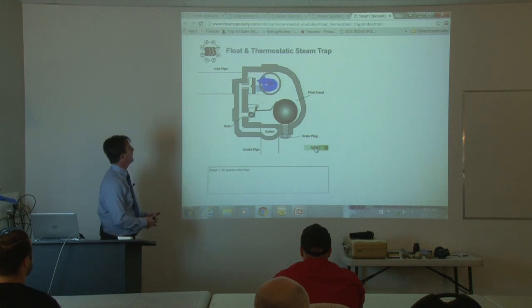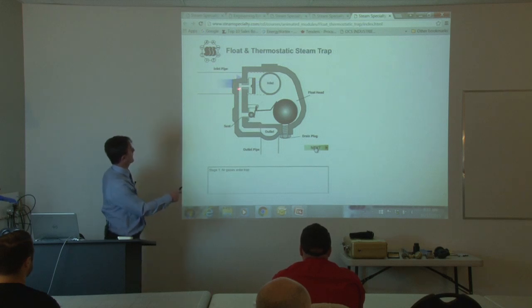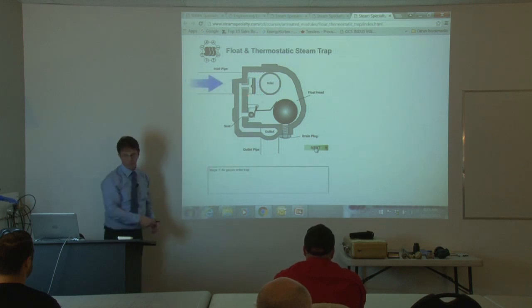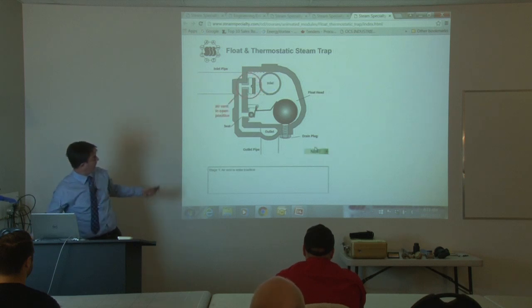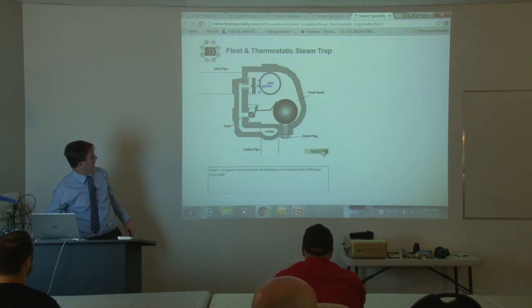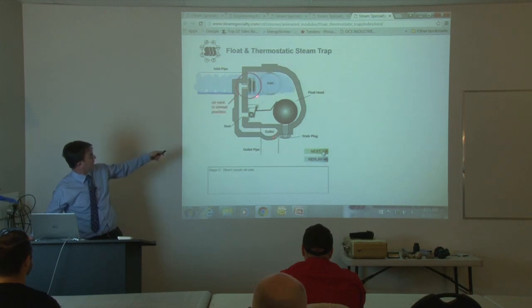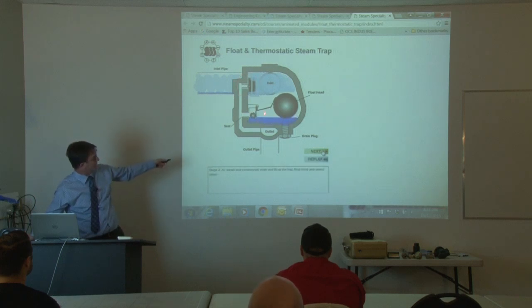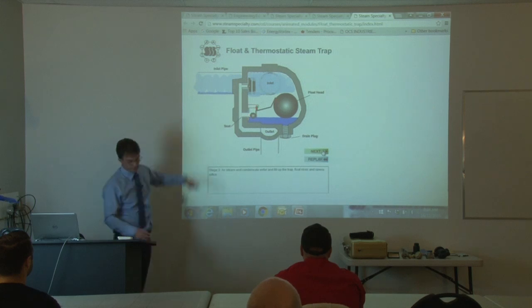Many different companies make float and thermostatic steam traps — Colton is definitely not the only one. This graphic from the Steam CD website shows the operating principle. At startup, the air vent element is open and air is allowed to exit the trap. Air and non-condensable gases pass through the separate chamber. As the temperature heats up inside the steam trap, the air vent closes off, condensate fills the body, the float rises, and the arm — with a kind of ball bearing welded to it — connects the float to a pivot point that opens and closes the steam trap.